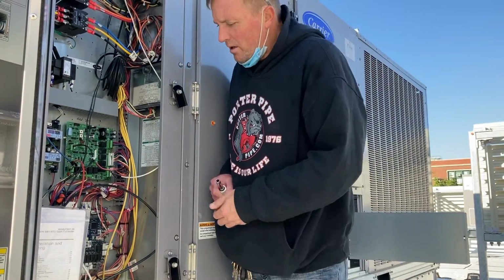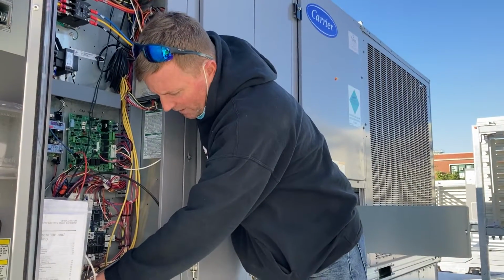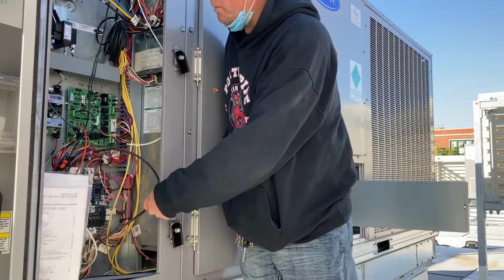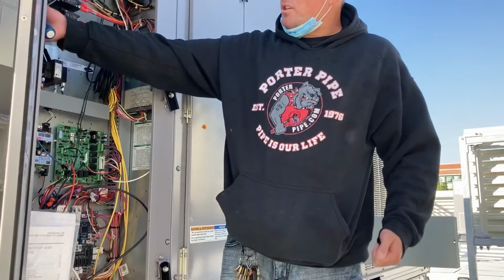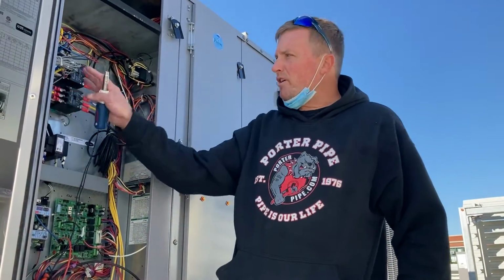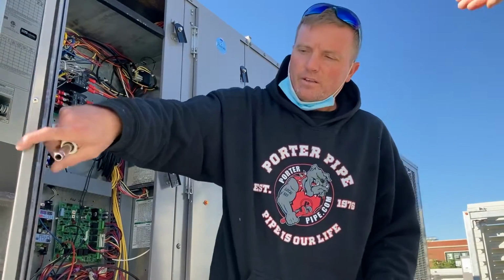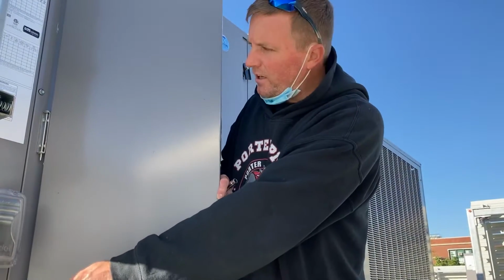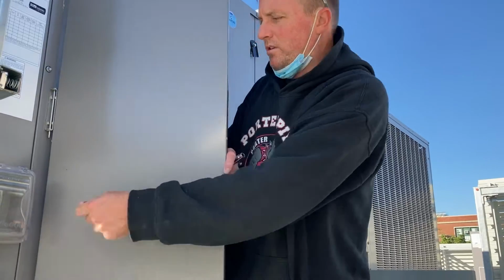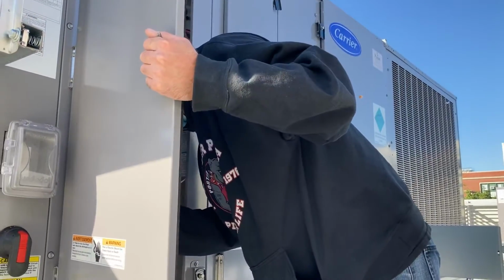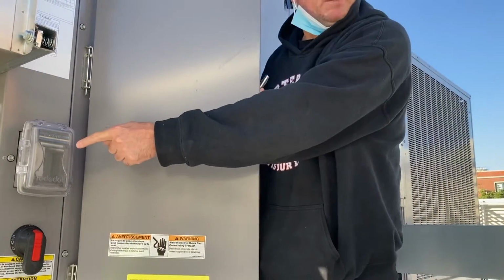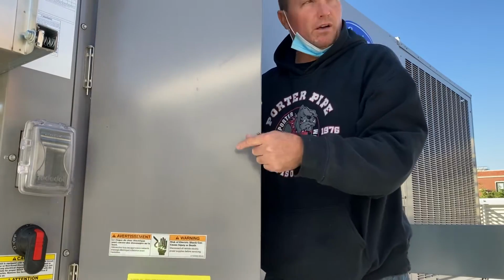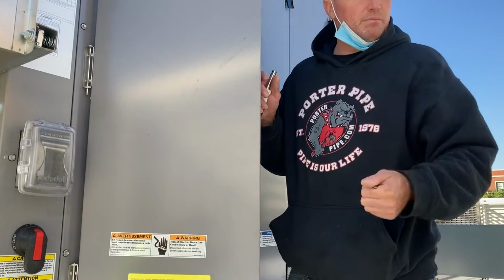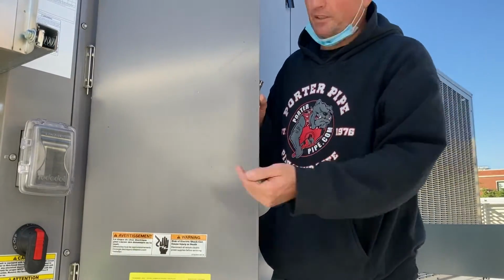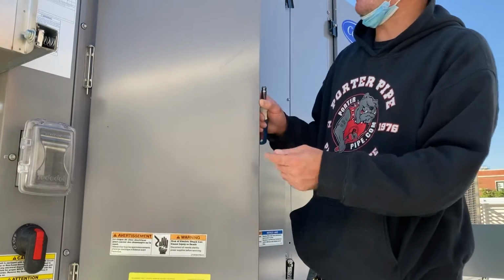Yep. This is obviously your duct static, as I said. We'll need to get the building pressure static. This is to shut the fan and anything else off. You also have a disconnect here, 120 volts, which is fed separately. Typically we can hook it up through our unit, but as the City of Chicago states, it's got to be on a separate 120, so that's on downstairs.